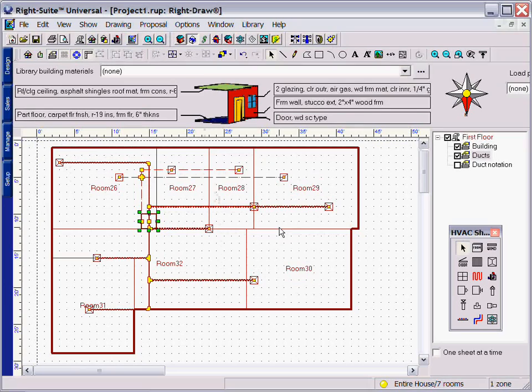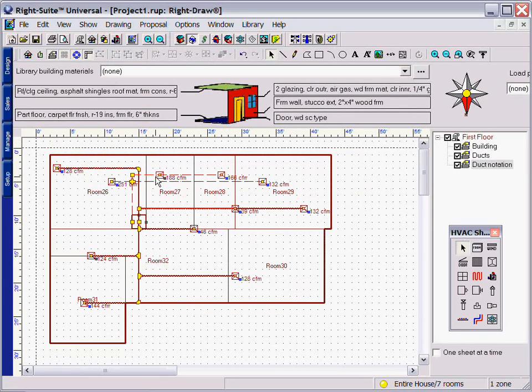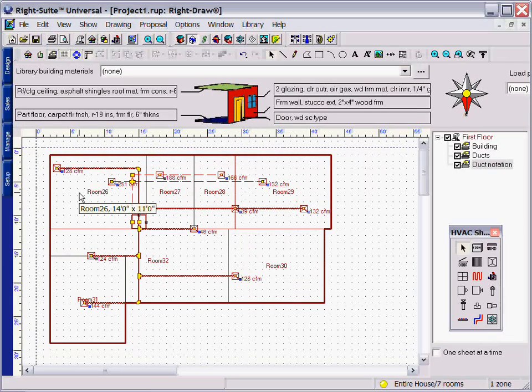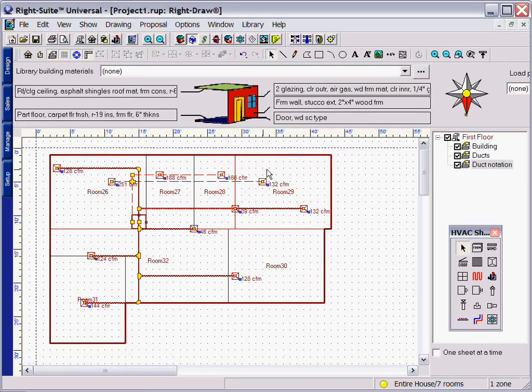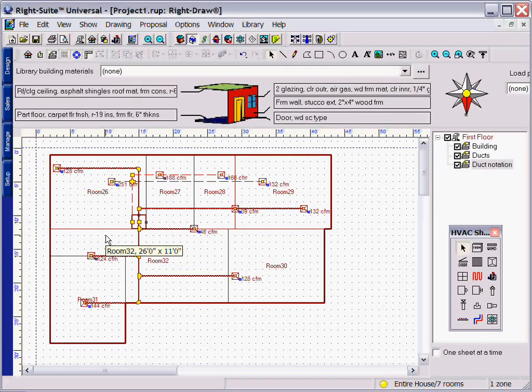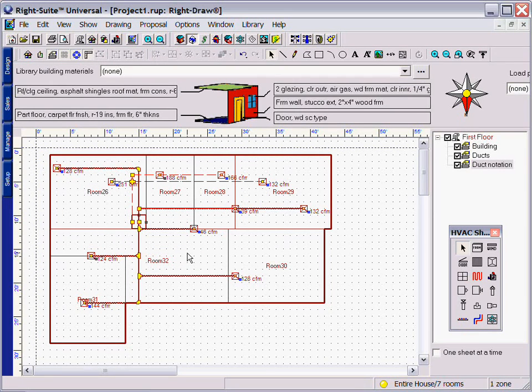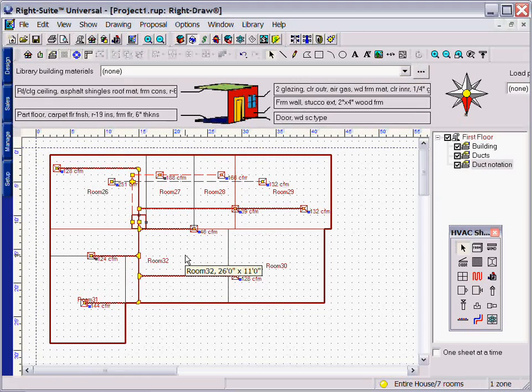Going back to your draw screen, it is easy to see why using Right-Draw can help you quickly and easily design a system. By looking at the air flows, you can balance your system on the screen. You can even diagnose problems by determining where there might be an error by matching the air flows to an existing system.